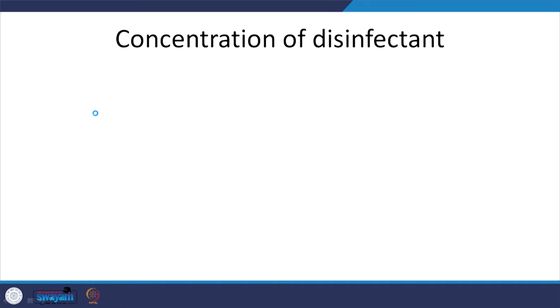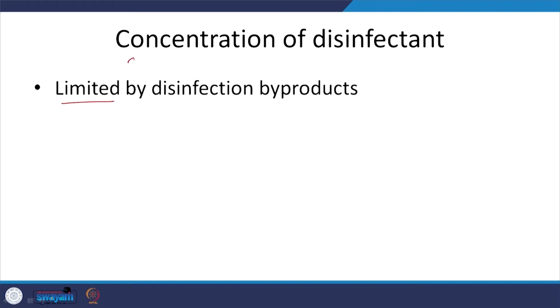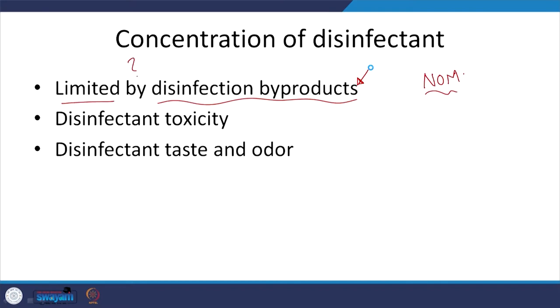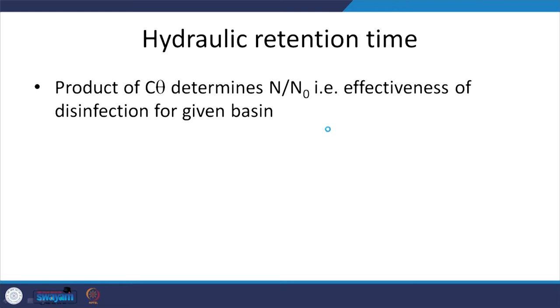The primary variable is the concentration of the disinfectant — it should not be too high, because then it will react with NOM and form harmful disinfection byproducts. The disinfectant itself may be toxic at high concentrations and can lead to odour and taste problems — as sometimes seen in India when high chlorine is added at the treatment plant. The retention time also plays a role.